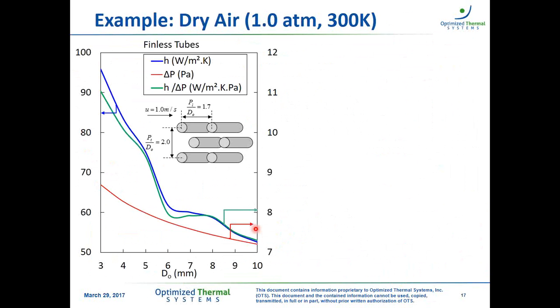Now, just to give some numbers as examples for dry air on a flow across a tube bundle, finless tube bundle, for constant velocity and constant pitch ratios, okay? The x-axis is the tube diameter, and on the left y-axis we have in blue the heat transfer coefficient, and on the right y-axis we have in red the pressure drop, and in green the ratio between the two. So what we're seeing here is that by reducing the tube diameter, we have a significant increase in heat transfer coefficient, though we also have an increase in pressure drop. But if we look at the ratio between the two, we're still benefiting from a tube diameter reduction, since the heat transfer coefficient increases faster than the pressure drop.